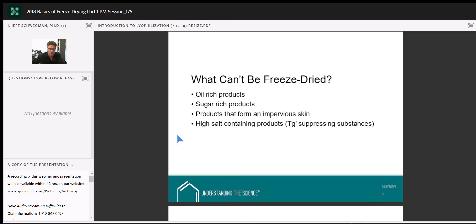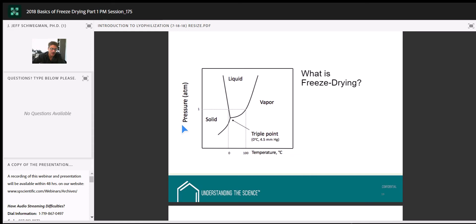Looking at the phase diagram: assume we're at 25°C and one atmosphere. We cool the sample down from liquid to solid. Then we create a vacuum — decrease the pressure — and we're still in the solid state. As we warm the sample at reduced pressure, we start to see ice crystals go directly from the solid state to the vapor state — that's sublimation, skipping the liquid state entirely. What we're left with is a dried solid with tiny pores where the ice crystals used to reside, which actually helps reconstitution when we add water back.